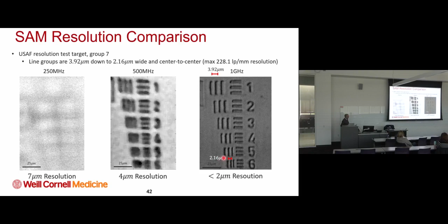And we can scan these resolution targets that are also standard for optical microscopy, but it turns out that the ink on the targets also has different acoustic contrast, so we can see it. And here, this is a kind of fractal structure with different groups and different spacing between the bars. Here I'm just illustrating that if we're looking at bars that are close to 2 microns, we cannot see them at 250, which has a theoretical resolution of about 7 microns. We cannot see them very well either with the 500, and then we can confidently say that the resolution is better than 2 microns, or at least 2.16 microns at a gigahertz.